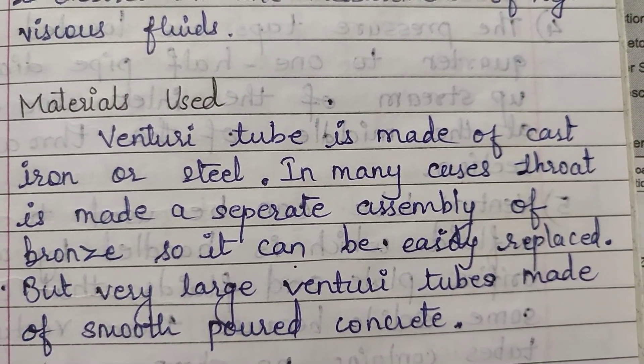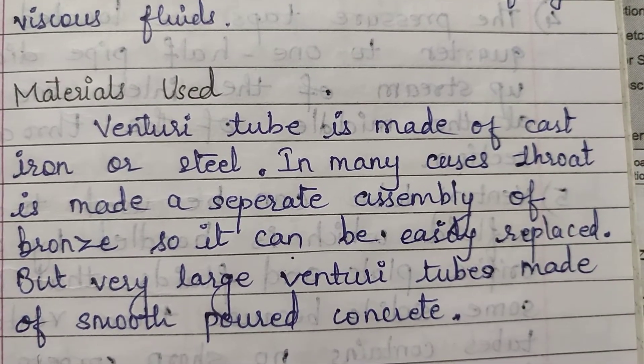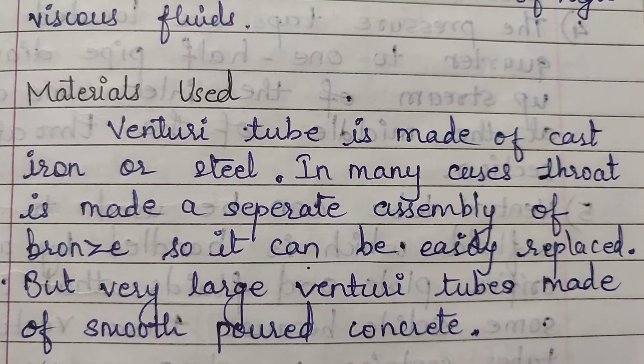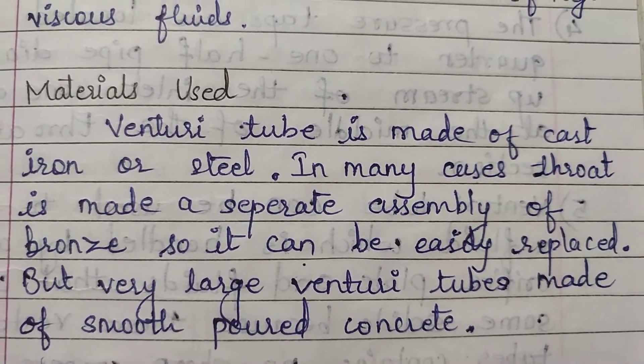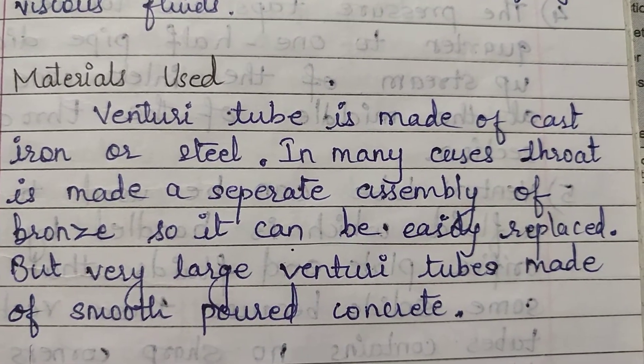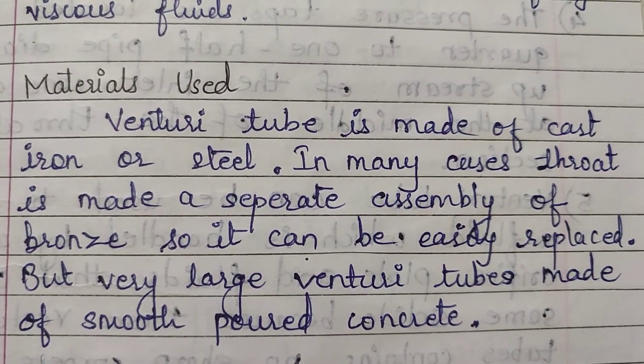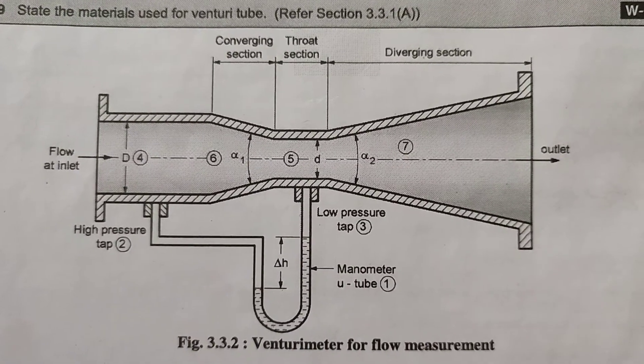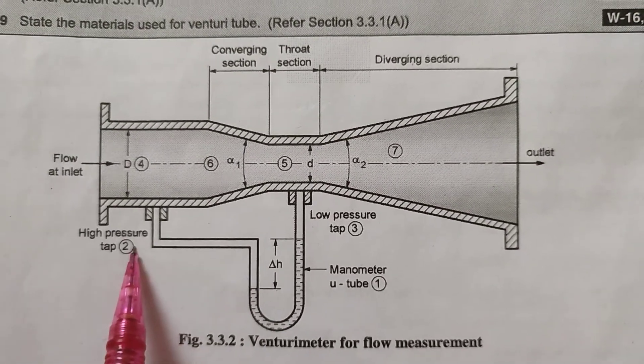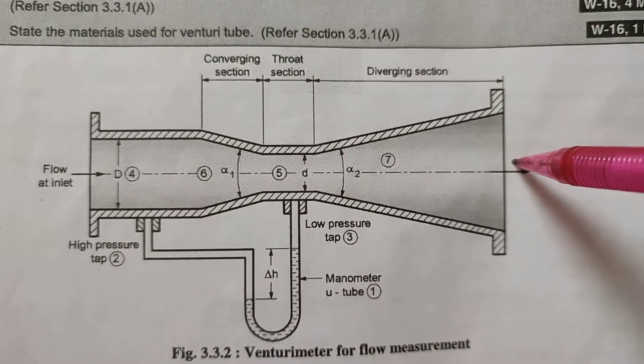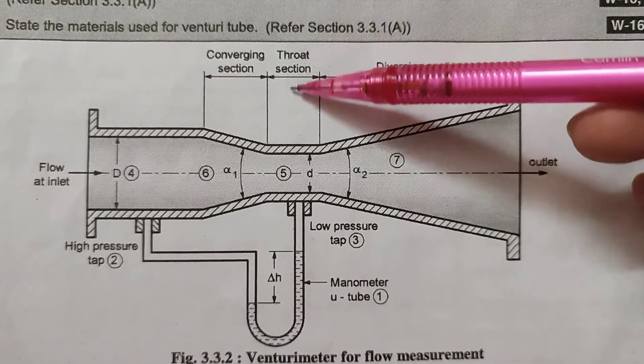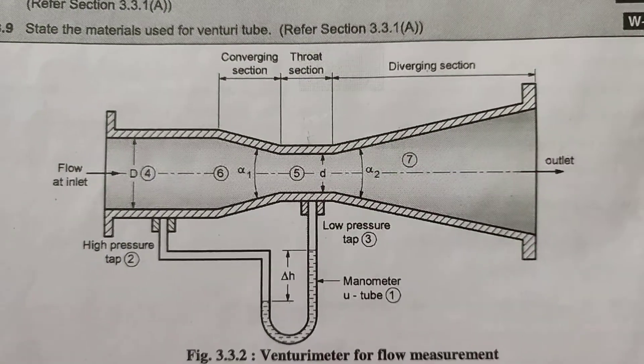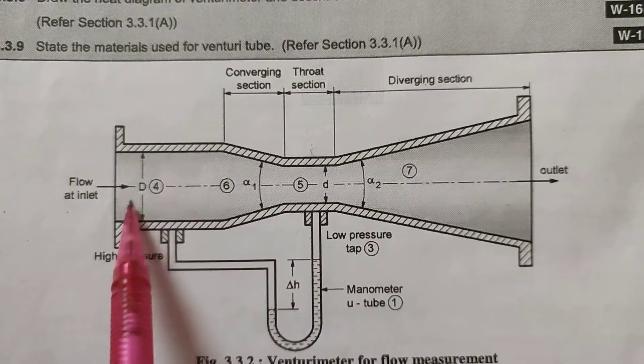Venturi tube is made up of cast iron or steel. In many cases, the throat is made up of a separate assembly of bronze so it can be easily replaced. Very large Venturi tubes are made of smooth poured concrete. Here is the flow inlet and here is the outlet. The throat section is made separate so that if there is a problem we can replace it. Venturi tube can be made of cast iron and steel.